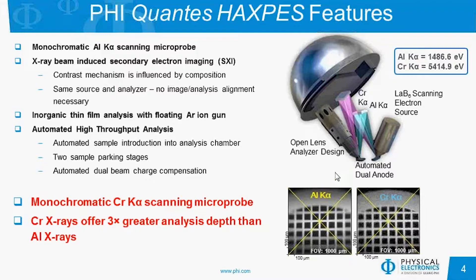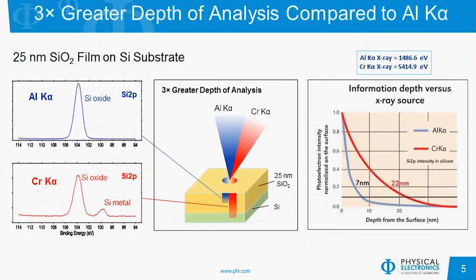Before going into applications, I'll show the gains from using a higher photon energy source. The first is three times greater depth of analysis. This example shows 25 nanometers of SiO2 on a silicon substrate. Using the aluminum K-alpha source, we can only see the silicon oxide. However, by using the chromium K-alpha source, we can see much deeper into the sample and see both the silicon oxide and the silicon metal without having to sputter. With a sample this thick using the aluminum K-alpha, one would have to sputter in order to see the underlying silicon substrate.